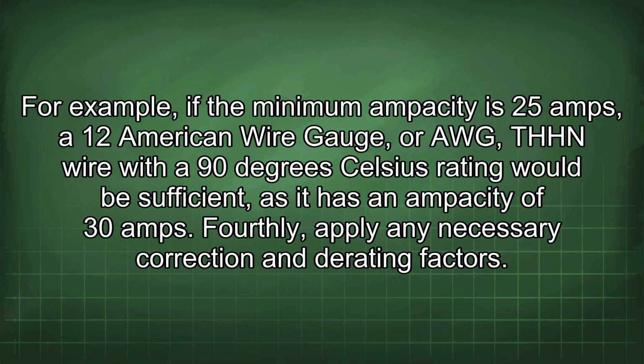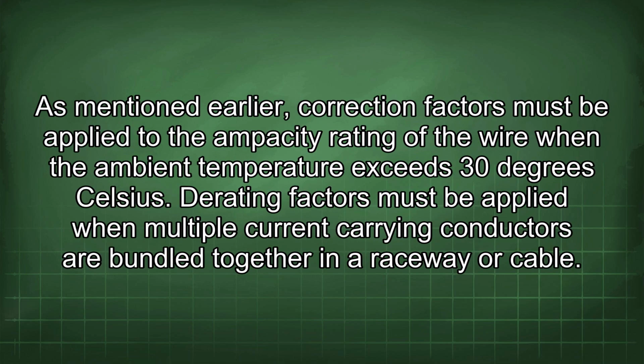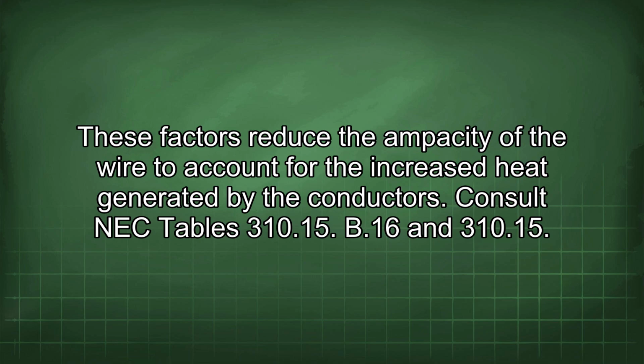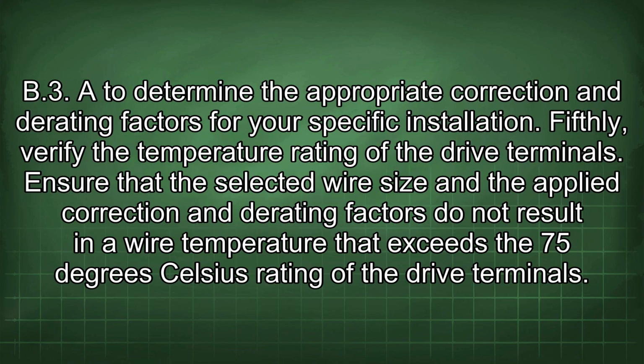Fourthly, apply any necessary correction and derating factors. As mentioned earlier, correction factors must be applied to the ampacity rating of the wire when the ambient temperature exceeds 30 degrees Celsius. Derating factors must be applied when multiple current-carrying conductors are bundled together in a raceway or cable. These factors reduce the ampacity of the wire to account for the increased heat generated by the conductors. Consult NEC Tables 310.15(B)(16) and 310.15(B)(3) to determine the appropriate correction and derating factors for your specific installation.